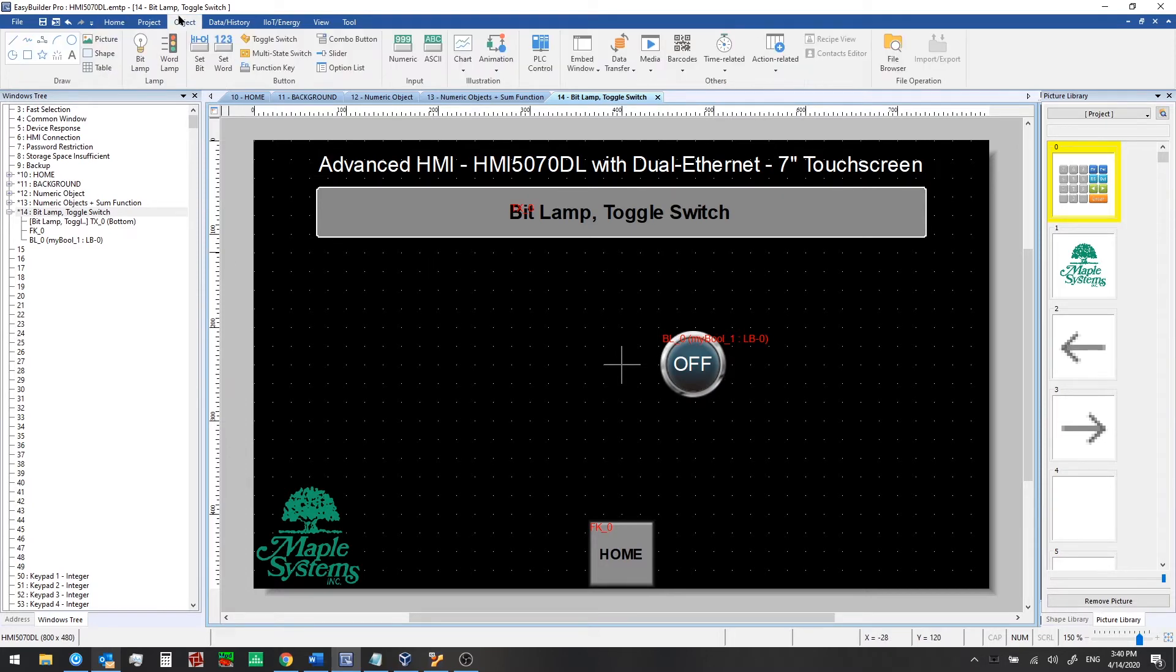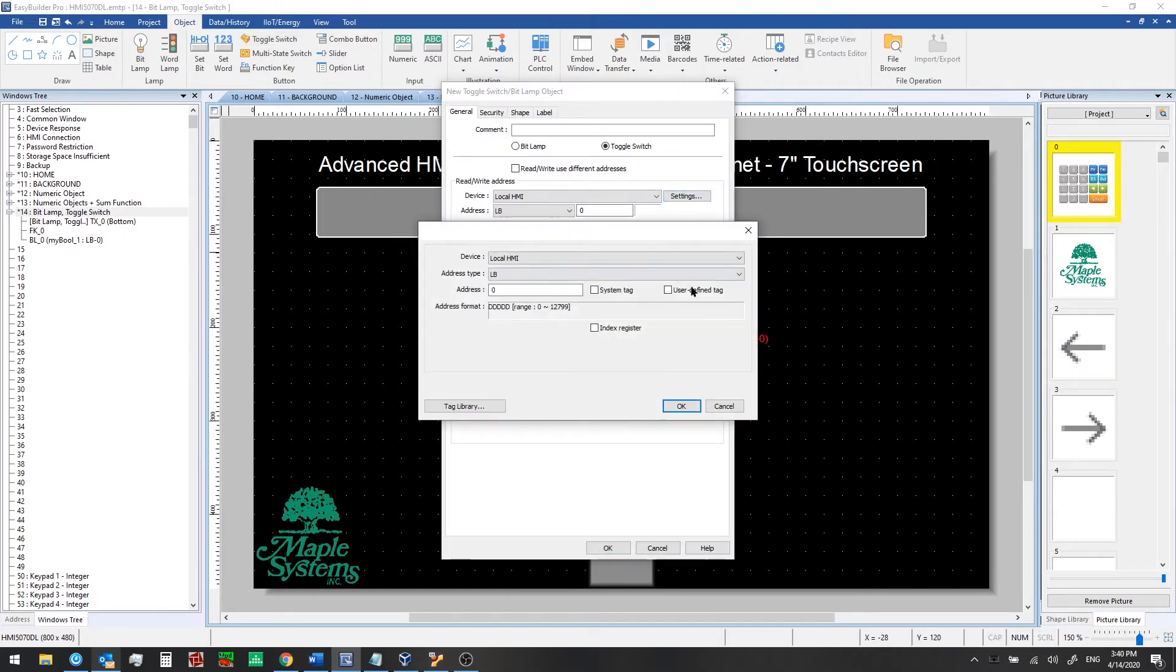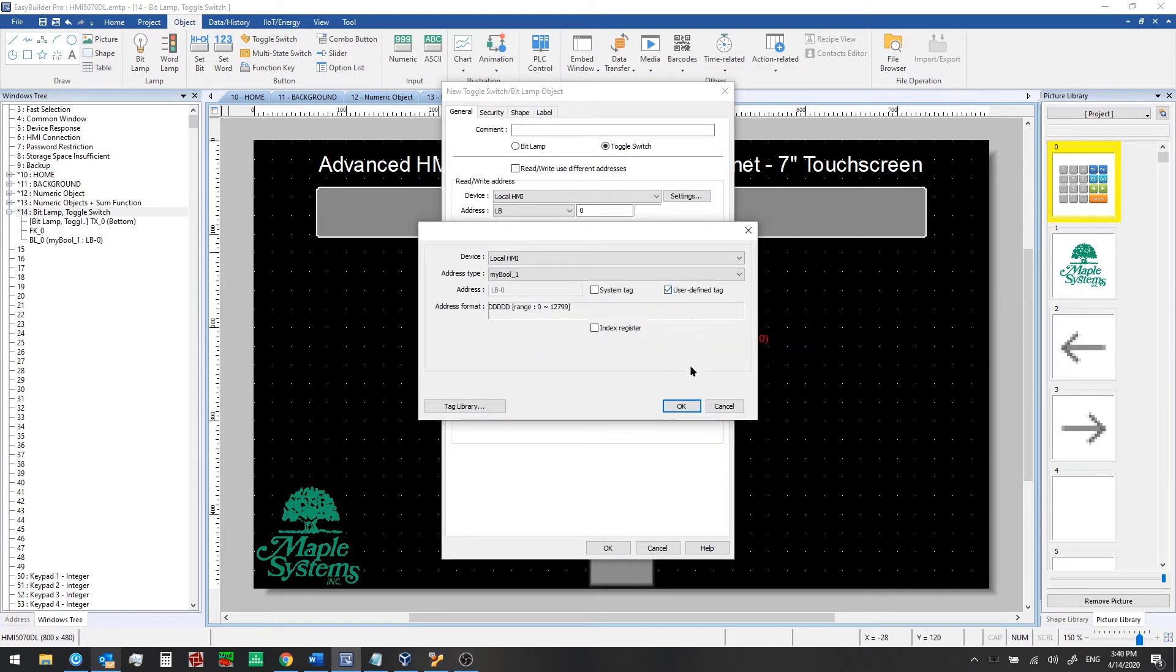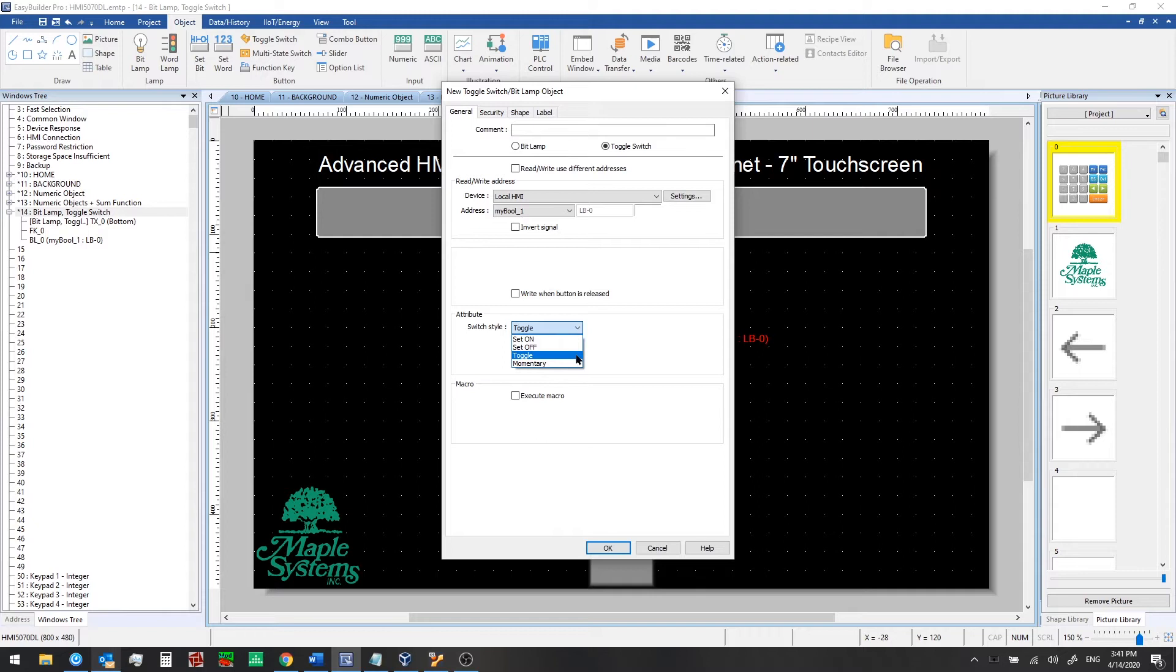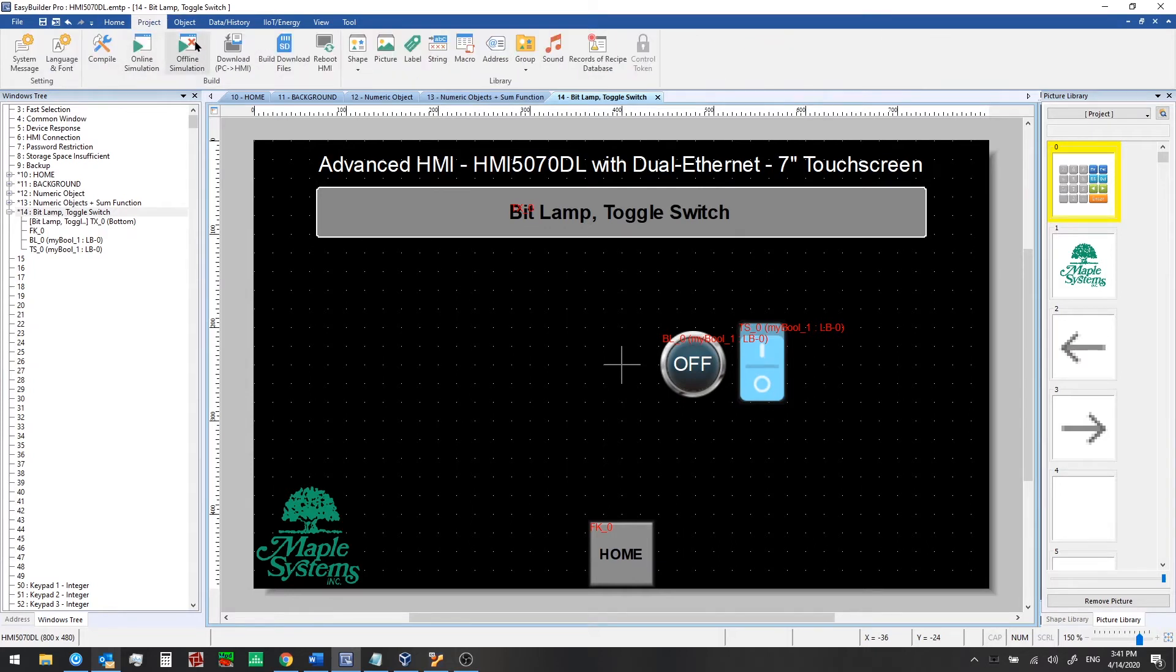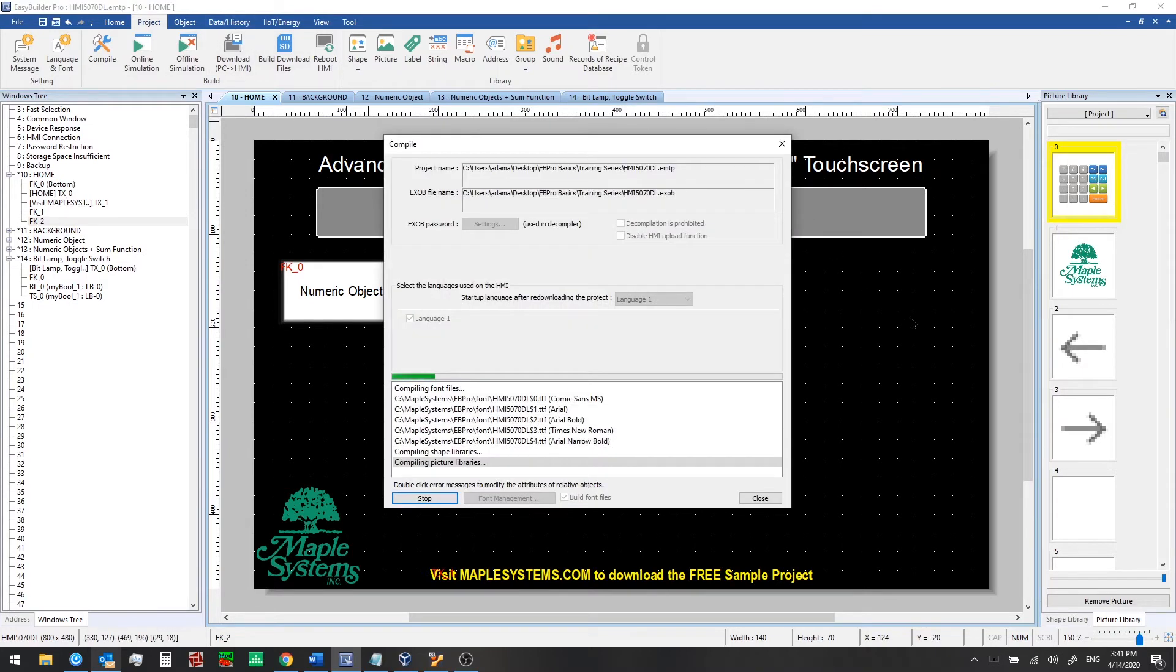And we'll go next and create a toggle switch. We'll use the same read and write address here, MyBool1. So this will be our way that we can toggle that bit. Toggle switch is selected here. And the switch style is toggle. You also have the option to do momentary. So we'll just flip it on for a moment and then it will go back off. We're going to use toggle for now. Take a look at the shape. This is what it will look like in the off and on state. We don't want to use any label on this one. So we'll click OK and then add this to our window too. Now we're going to go ahead and save this. And then run a quick offline simulation and take a look at what it looks like. Note that we also added this new window for this functionality. And on the home tab we have that function key to take us to that window.